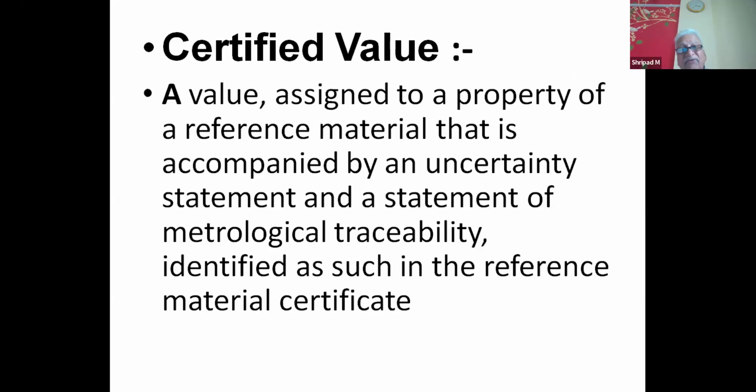Then the certified value is also an important terminology that we need to understand. It is a value assigned to the property of the reference material that is accompanied by an uncertainty statement and a statement of metrological traceability, identified as such in the reference material certificate.